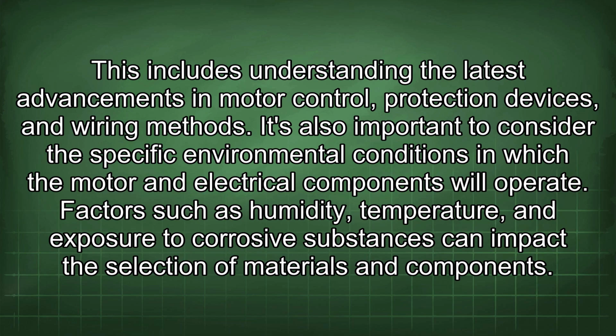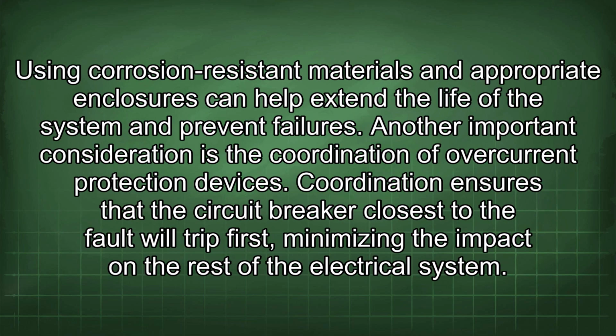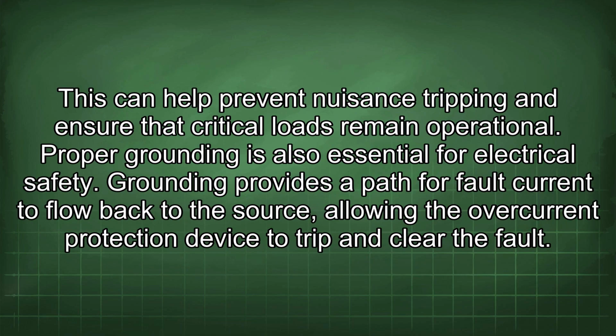Factors such as humidity, temperature, and exposure to corrosive substances can impact the selection of materials and components. Using corrosion-resistant materials and appropriate enclosures can help extend the life of the system and prevent failures. Another important consideration is the coordination of overcurrent protection devices. Coordination ensures that the circuit breaker closest to the fault will trip first, minimizing the impact on the rest of the electrical system. This can help prevent nuisance tripping and ensure that critical loads remain operational.